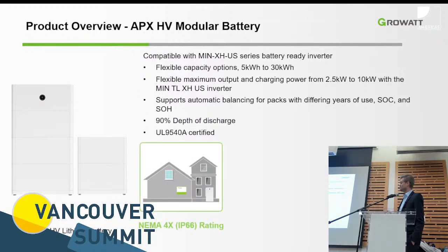The depth of discharge is 90%. That's typically industry standard, so you use most of the capacity that's available, and it's fully UL 9540A. The presentation here says certified. That's the marketing team. As we know, it's not a certification, it's a testing.